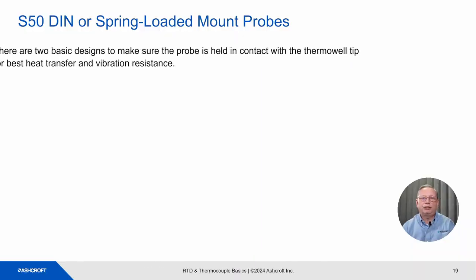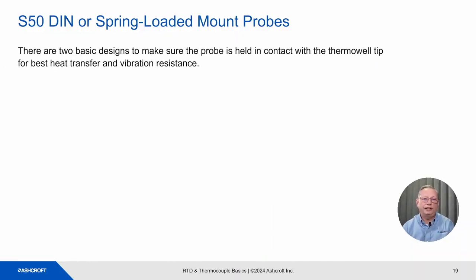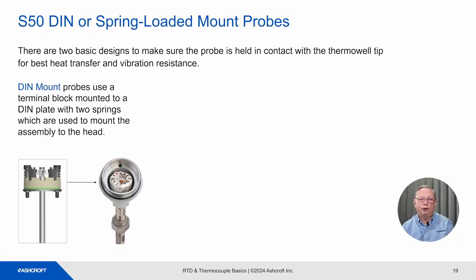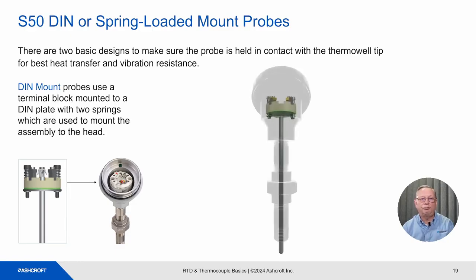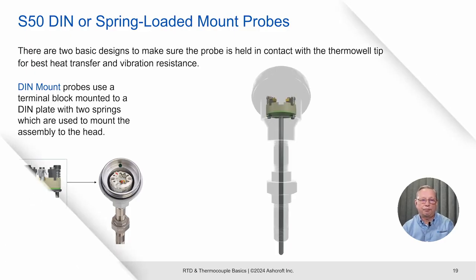There are two basic design configurations for S50 probes, a DIN mount or spring-loaded mount. Both designs make sure the probe tip is held in contact with the thermowell tip for best heat transfer and vibration resistance. DIN mount probes use a terminal block attached to a DIN plate with two springs and screws. The screws thread into the head and the springs allow the DIN plate to move up and down when inserted in the thermowell. The spring will hold the probe against the tip.